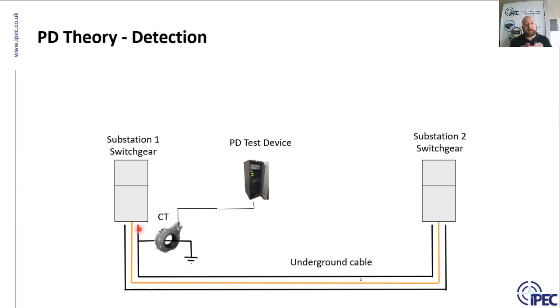If they are directly connected, if the earth is directly connected, what it means is that the HFCT must be installed on the core of the cable. Normally that also means that it must be installed inside the termination. So again, the only place where you can separate the two sometimes is on the core of the cable. Case by case, we look at that with customers, and we're always happy to help and consult if anybody is in doubt.